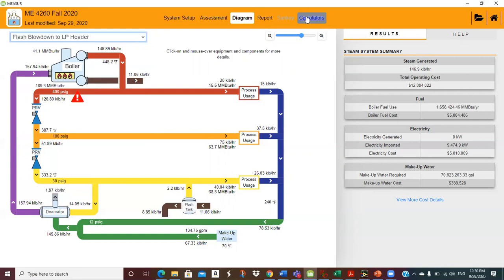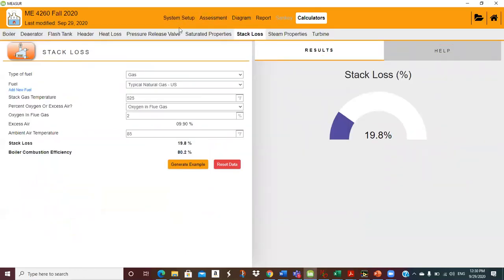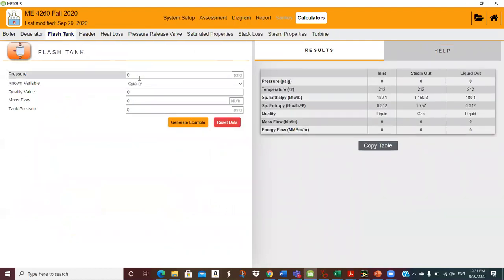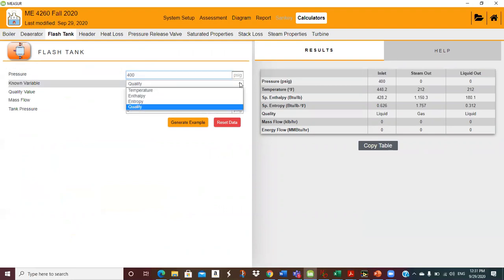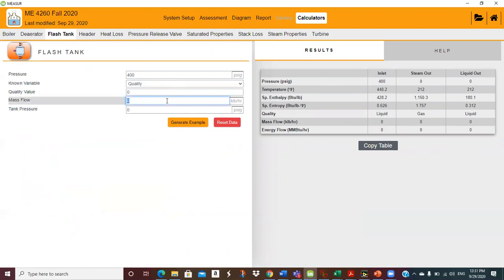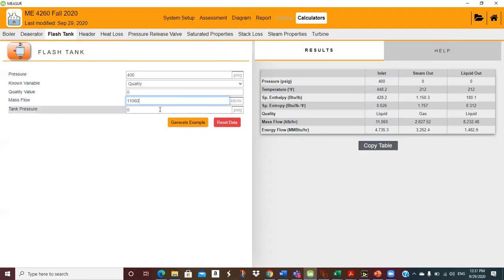See, this blowdown — if I don't connect it to a flash tank or heat exchanger, this blowdown is going to sewer. It's gone. So 2,200 pounds an hour, that's a fair amount of steam. Do they have a flash steam calculator on here? Yes — flash tank. So pressure 400, quality zero — it's saturated liquid. Mass flow 11,060, tank pressure 30. Steam out: mass flow 2,203.55. That's the process that's going on.